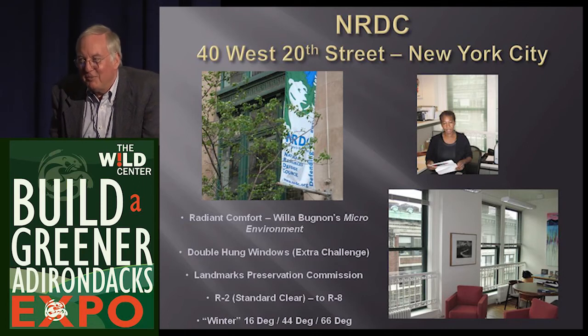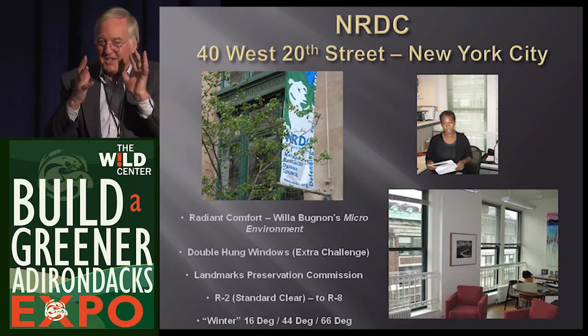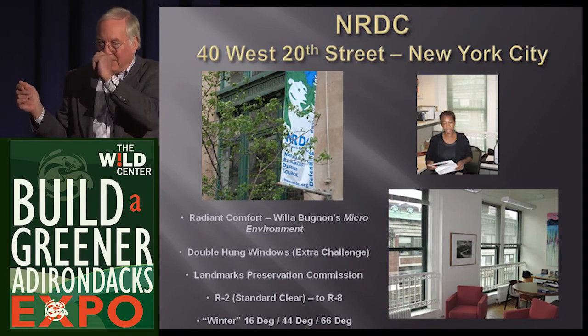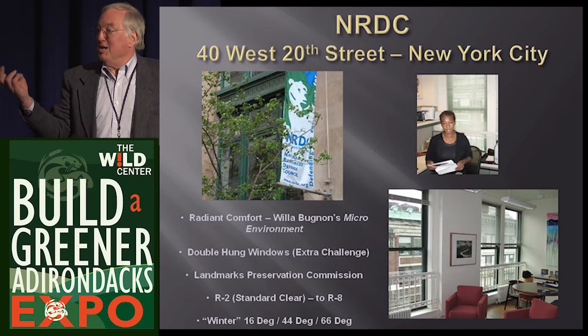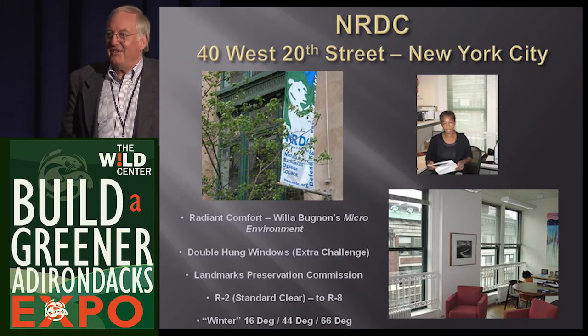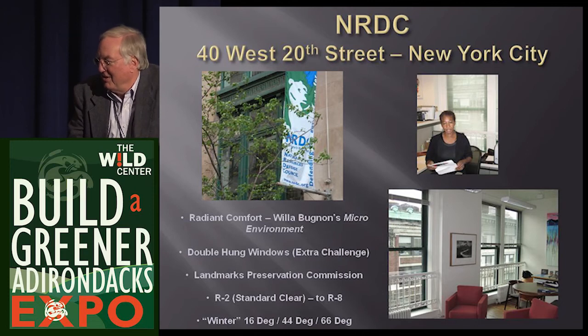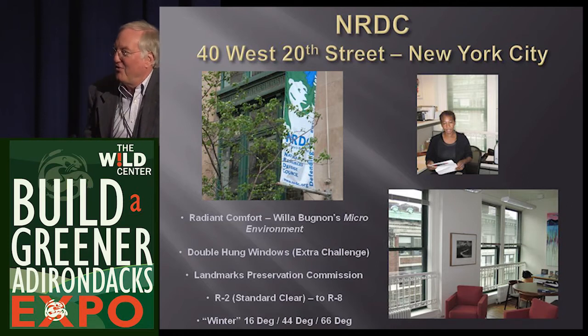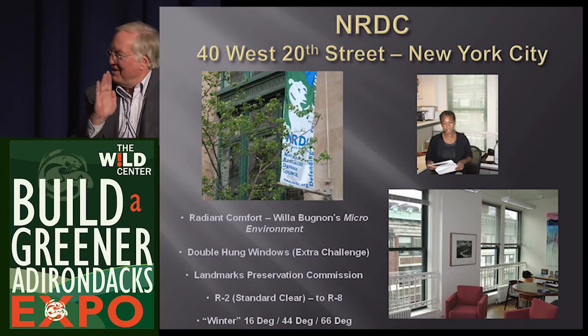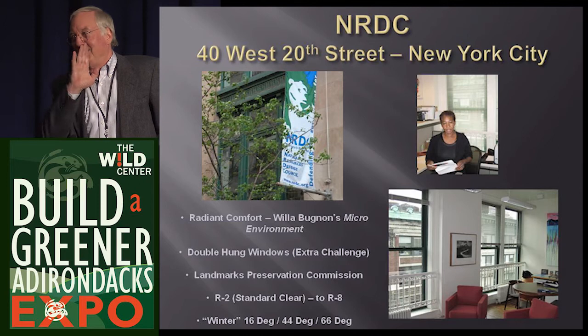Willa is my prototype of comfort. A 94 single-spaced page study on comfort of people sitting next to windows concludes there are five basic factors determining human comfort: number one is air temperature, which accounts for only about half of how you feel. Number two is radiant comfort - the radiation your exposed hand or face sees, looking at a warm wall or cold window. Number three is relative humidity, number four is air velocity, and the fifth is human activity level.